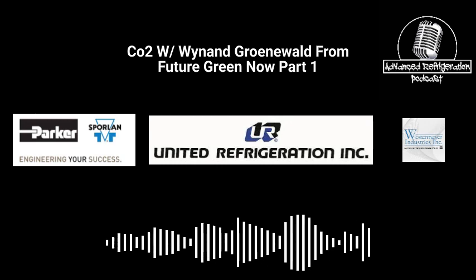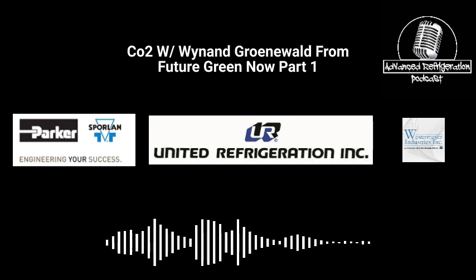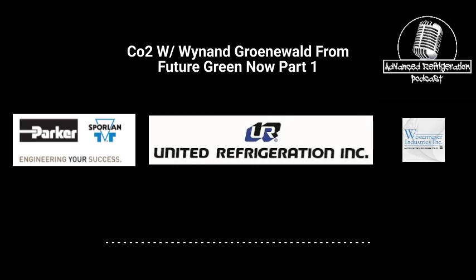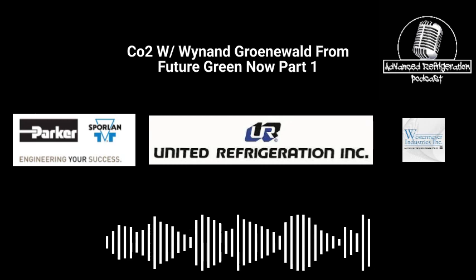Yeah. Well, I talked to Ray Kelly about this when I met up with him in California. The idea is that because it's a lower quality of liquid than what you typically get, and more susceptible to pressure drop, if you evenly give each case a little bit of flash gas, then it's not as bad as having total vapor at the end. That was his thought, but now I'm thinking otherwise.